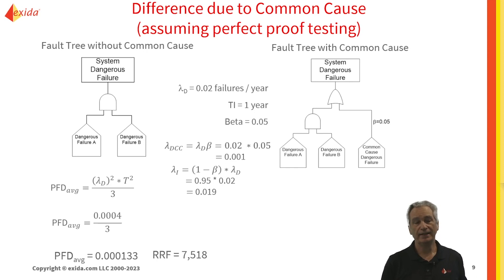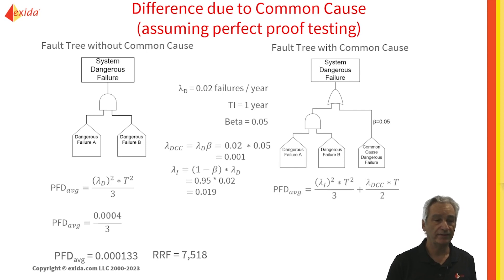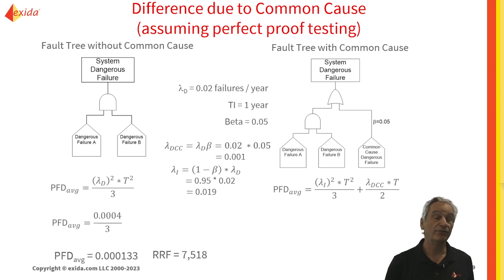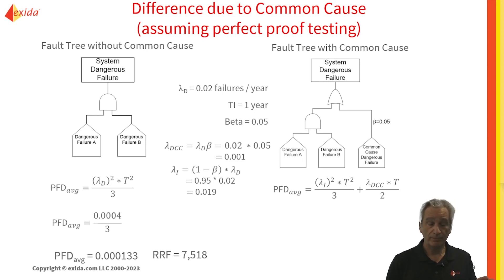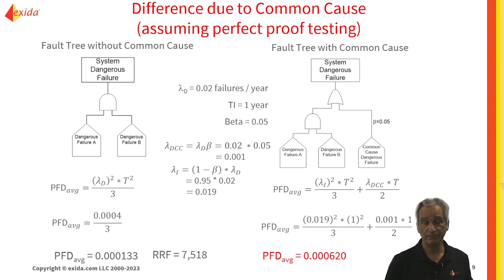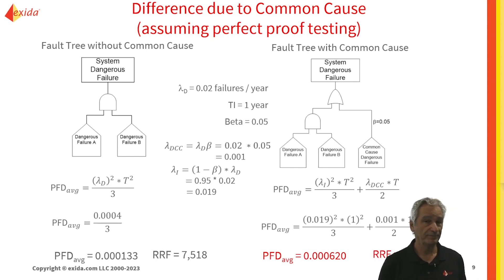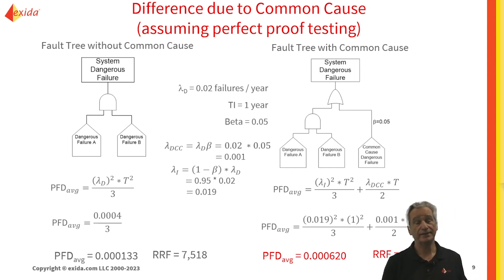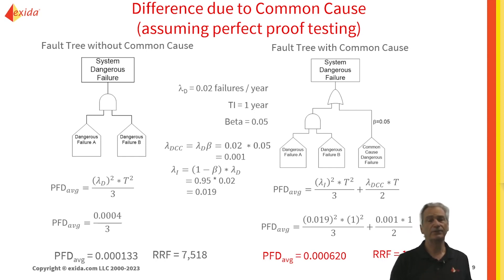Now on the right-hand side, the AND part is again lambda_I squared times t squared over 3, but now we have to add in the PFD average for the common cause, which will be lambda_CC times t over 2. If we plug in our numbers and do the math, we end up with a PFD average of nearly five times more than we had before, which means our risk reduction factor is almost five times less. And this is using only a 5% beta — if we were to use 10%, the gap would be even wider.